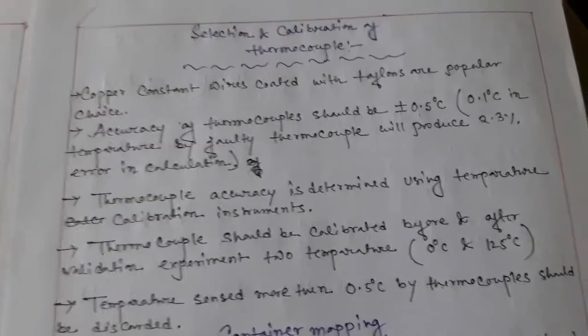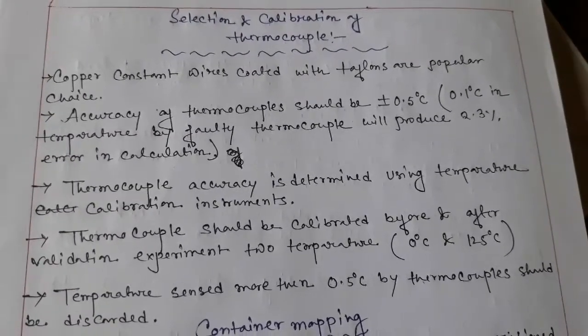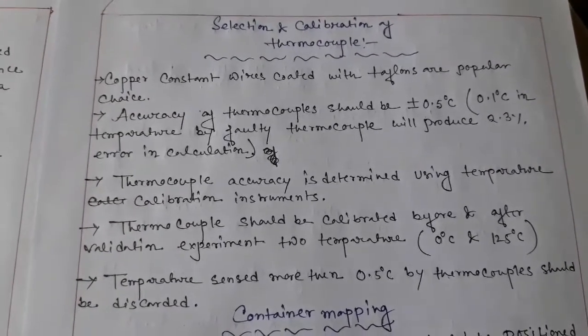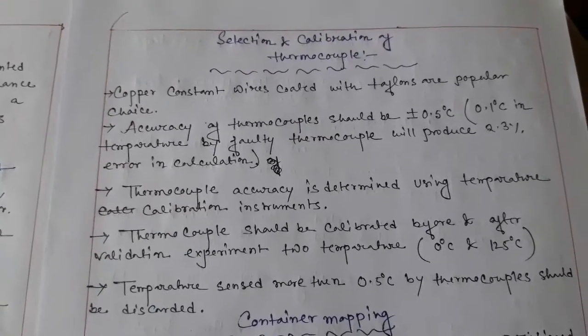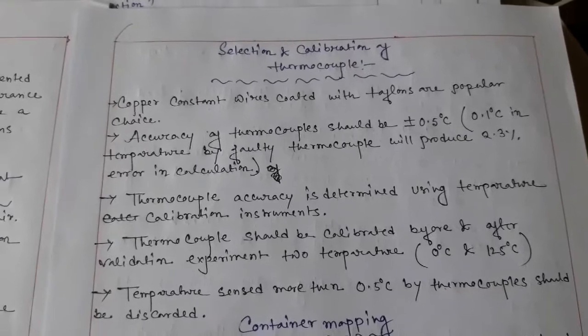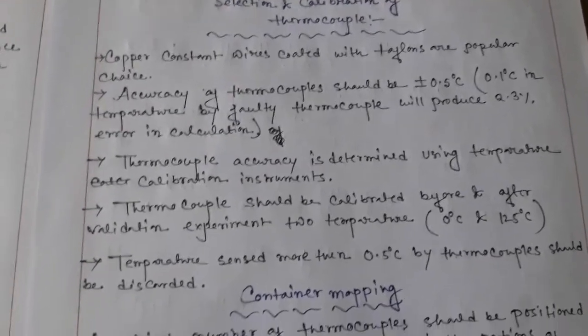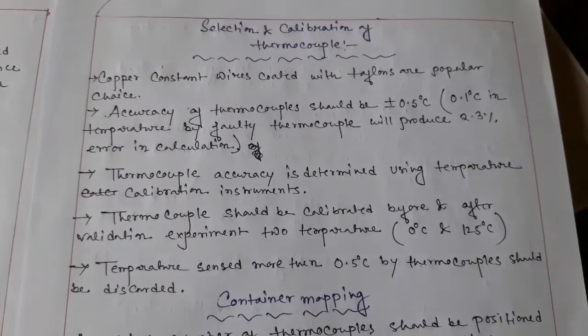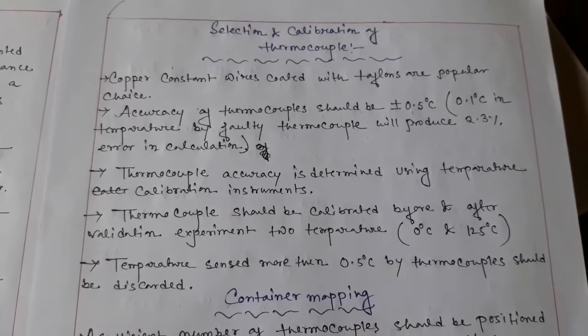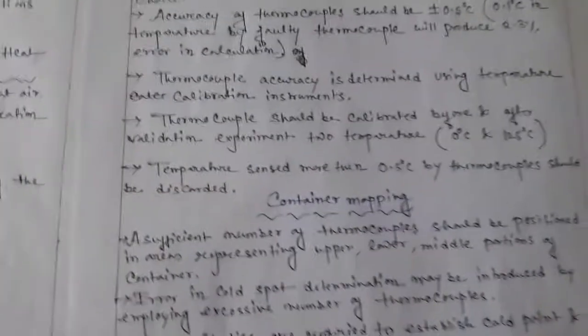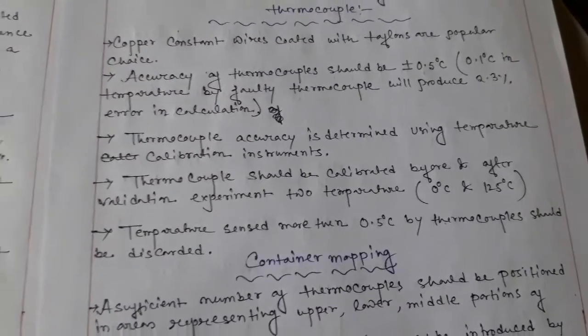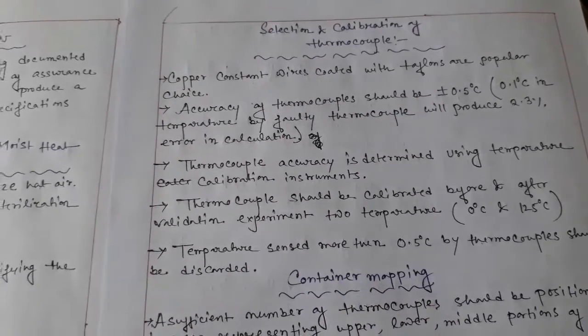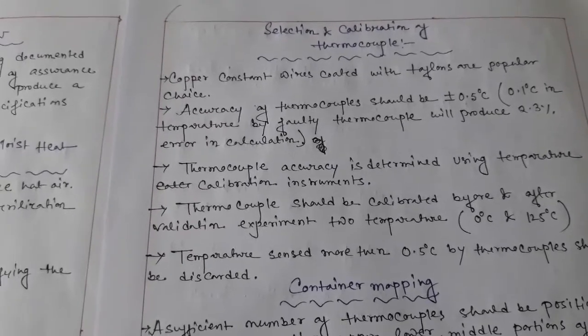Thermocouple accuracy is determined using temperature calibration instruments. Thermocouples should be calibrated before and after the validation experiment at two temperatures: 0 degrees centigrade and 125 degrees centigrade. Any temperature difference of more than ±0.5 degrees centigrade shown by a thermocouple should be discarded. These points must be followed for the validation of the autoclave.